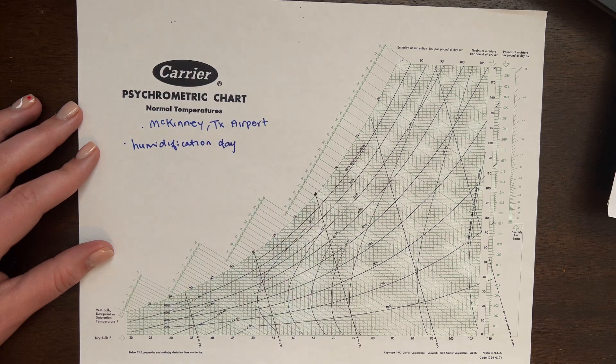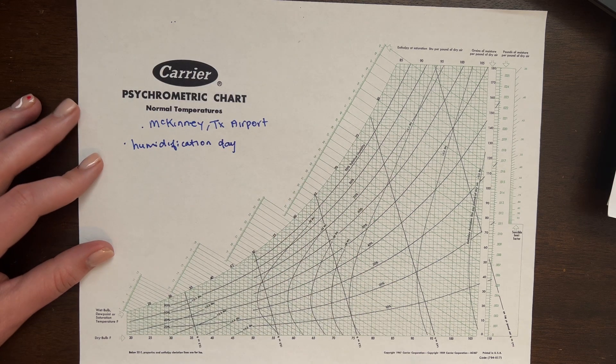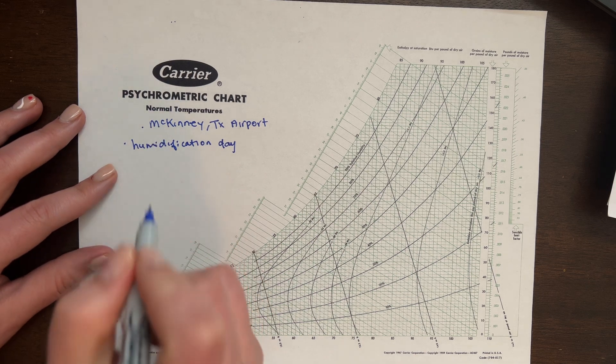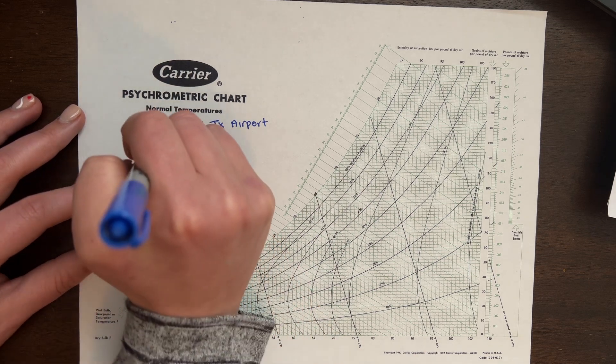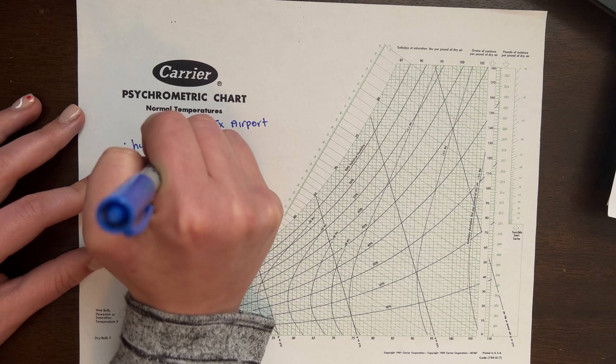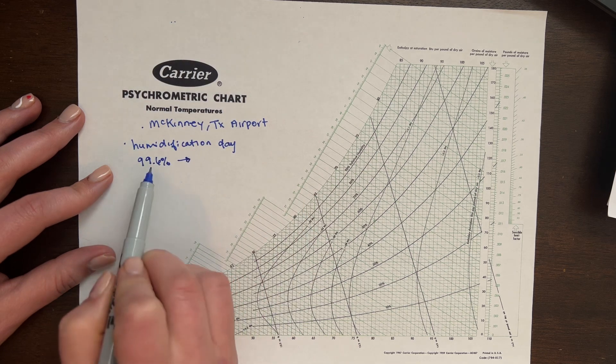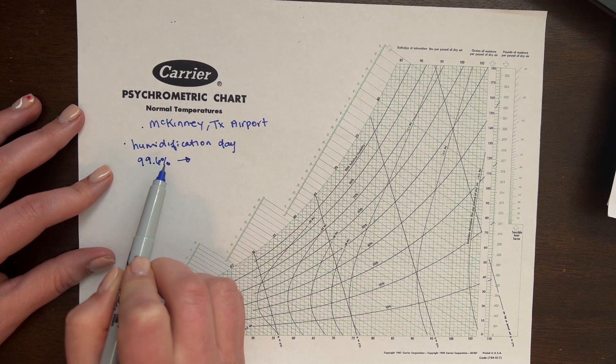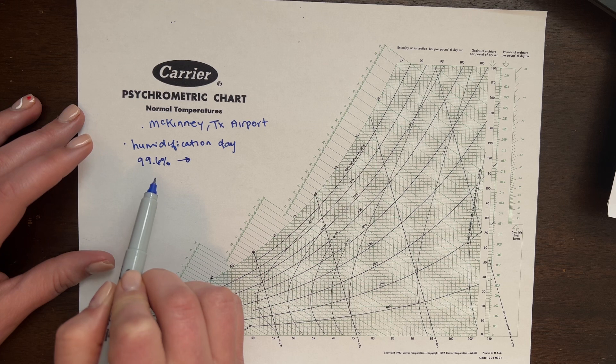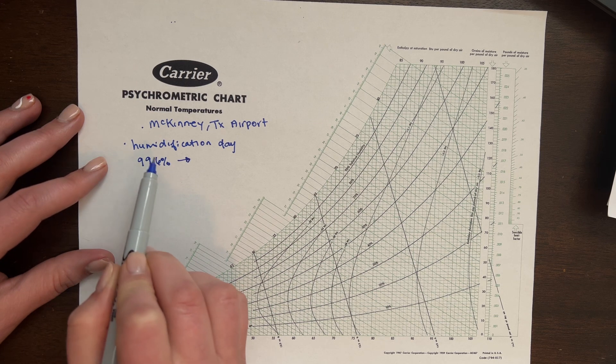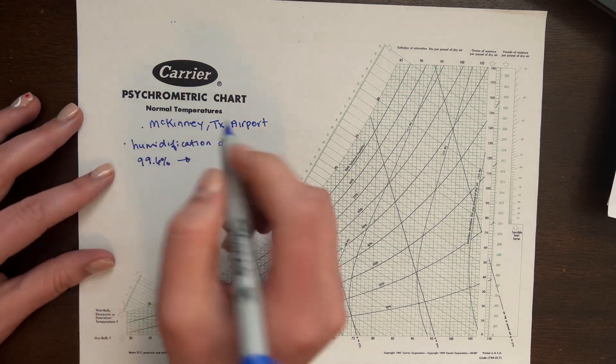And I'll use this information in another example to size a humidifier. Okay, so we have a humidification day, and I'm going to use the 99.6% day. That just means how often or how likely are you going to experience this day. It's going to be like 0.4% of the entire year you're going to experience this humidification instance.